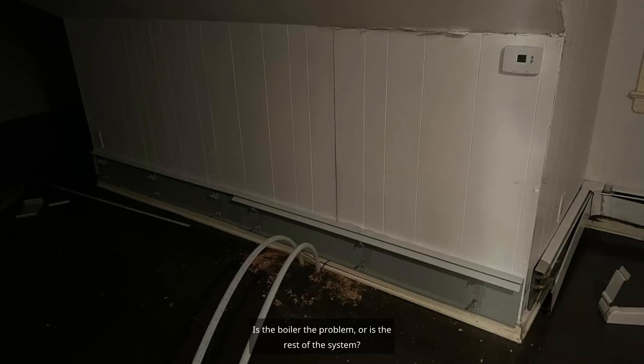Question 3: Is the boiler the problem or is the rest of the system? I see this constantly — a homeowner gets a quote for a new boiler when the actual issue is painted-over fin tube, a stuck zone valve, an airbound loop, or a dead circulator pump. Each of those is a few hundred dollars to fix. None of them needs a new boiler. Before you replace the heart of the system, make sure the rest of it is actually working.